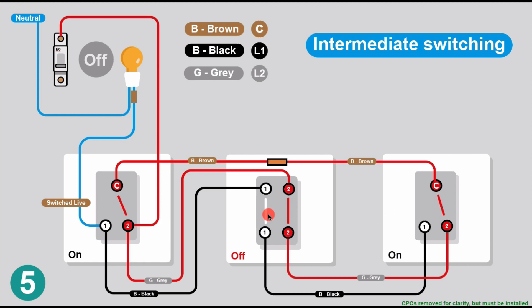We've walked back to the intermediate switch and switched it off, so the switching is now on-off-on. Following the power through the common, through the intermediate, we get that loop again going back to the MCB. Going the other way through the grey, there's a loop there too - not getting to this connection. So the light is off.